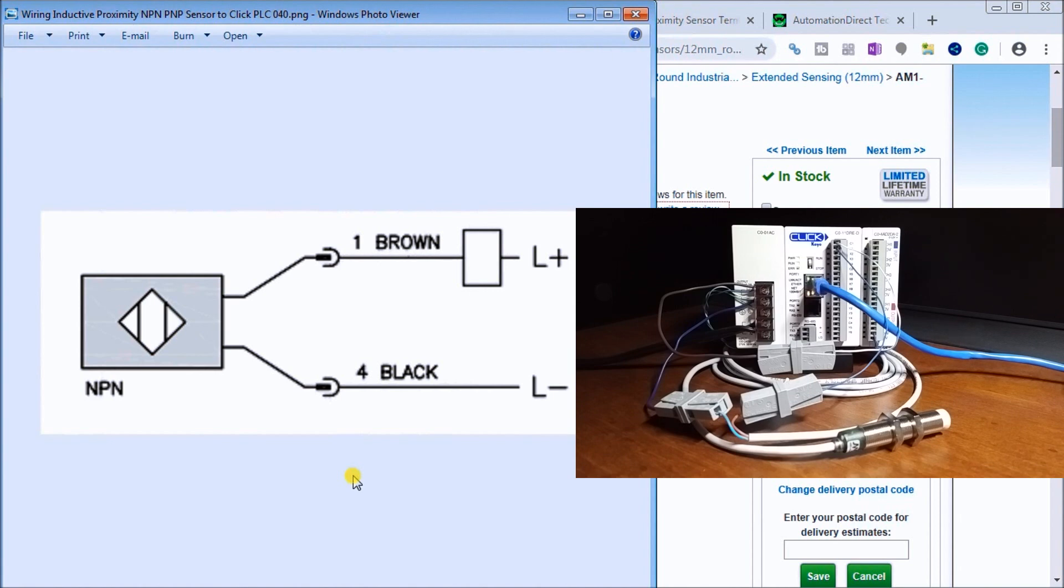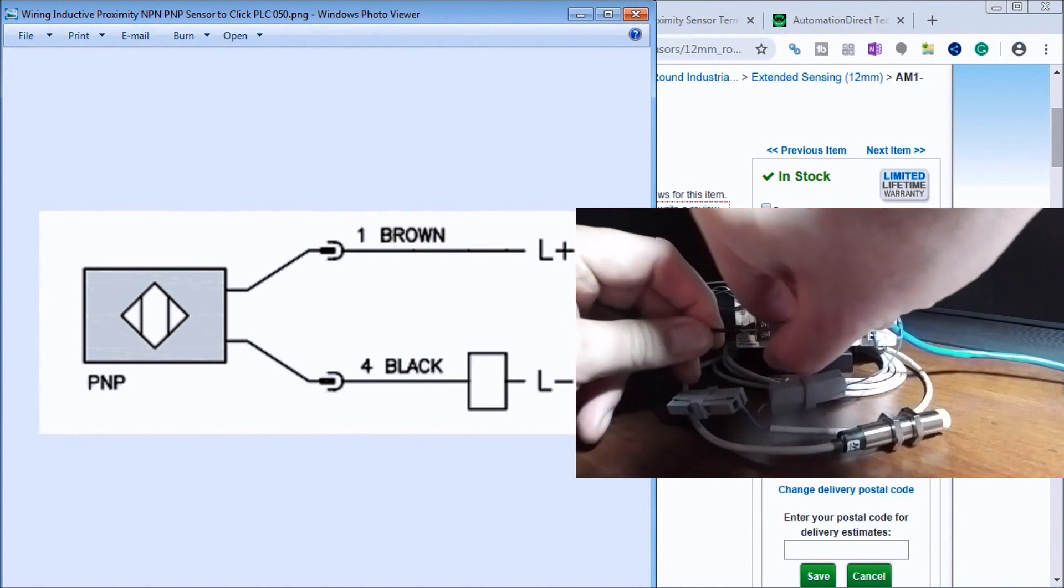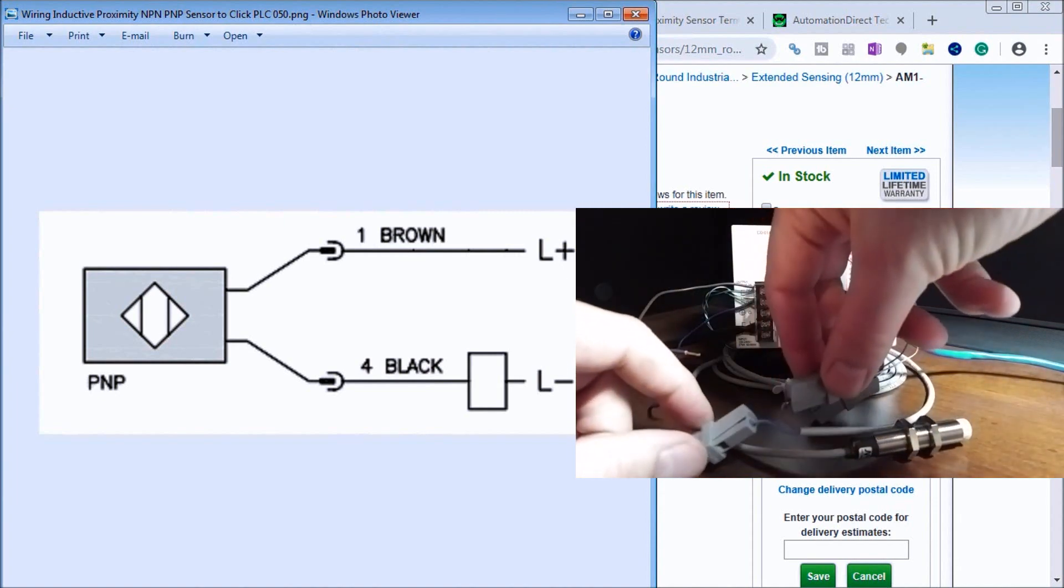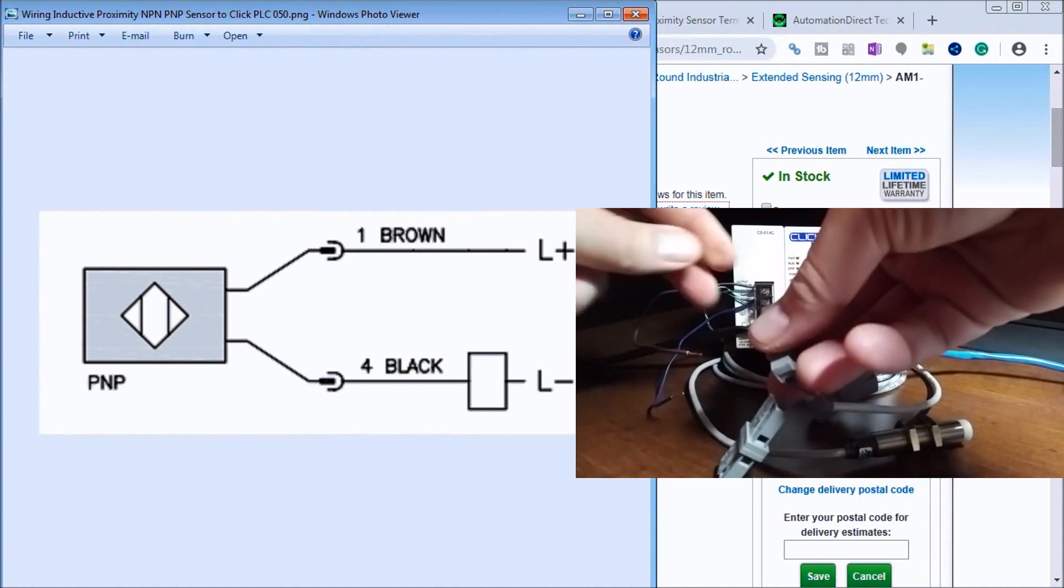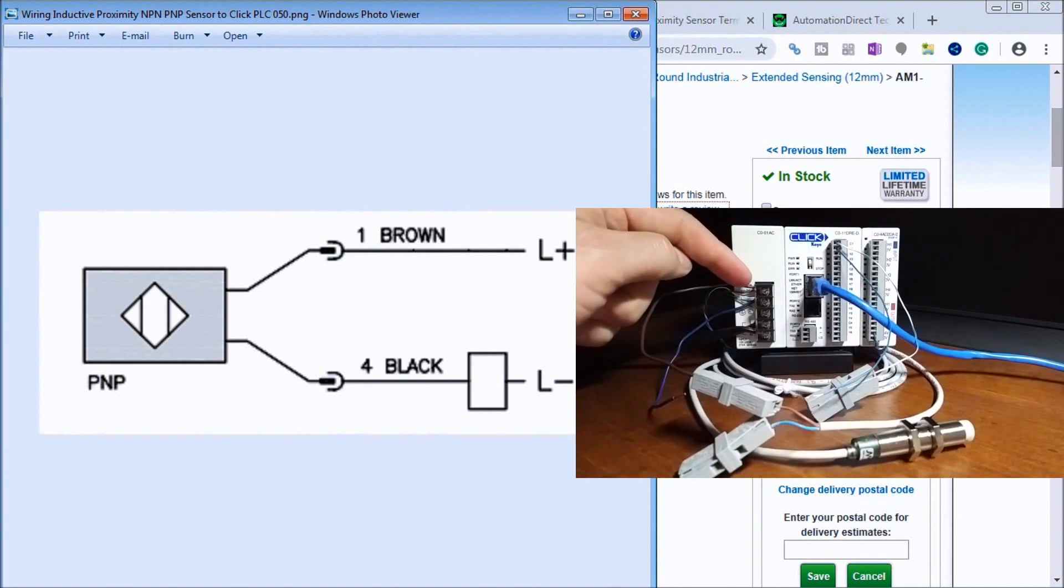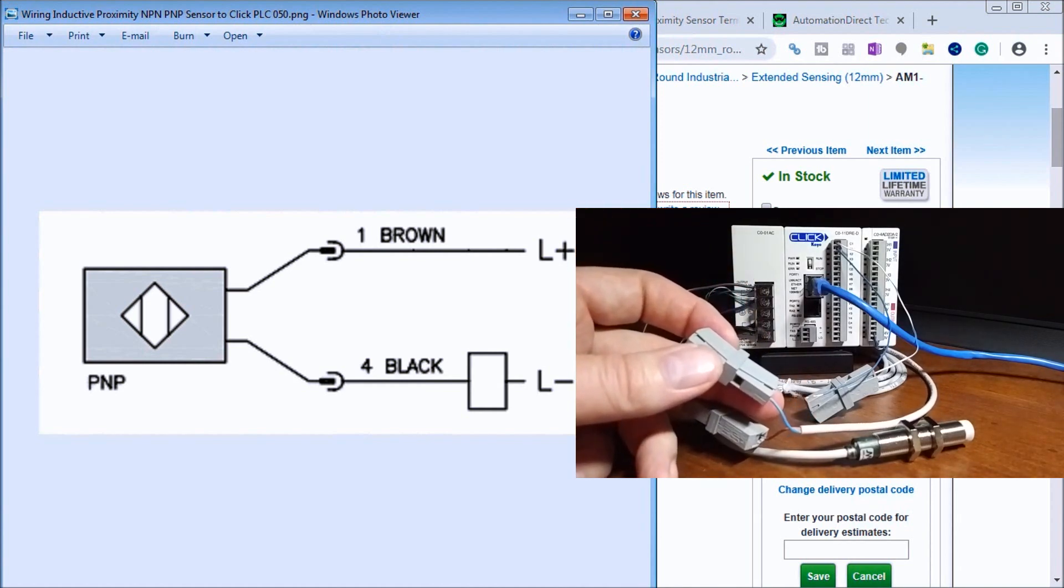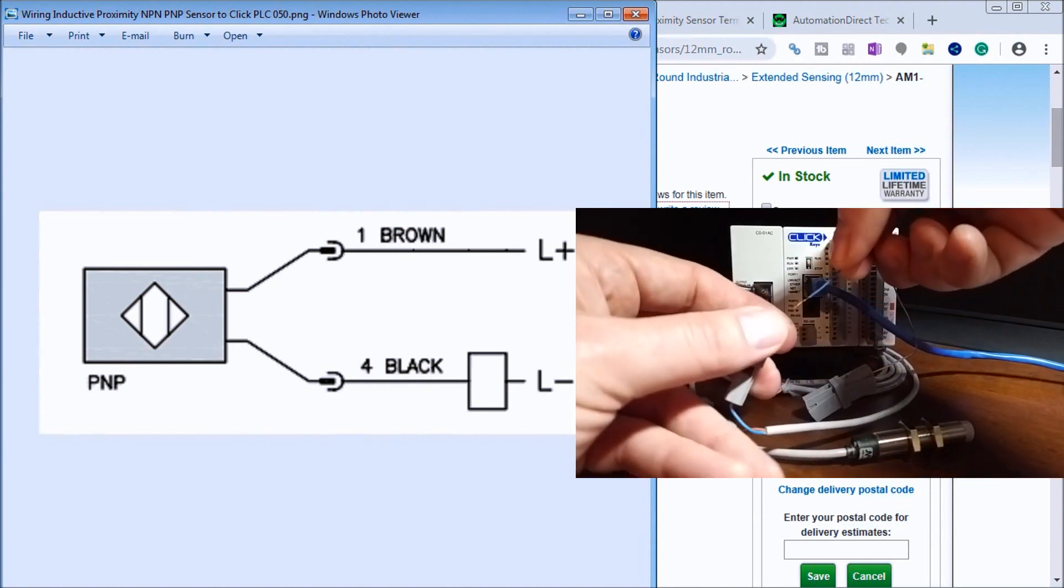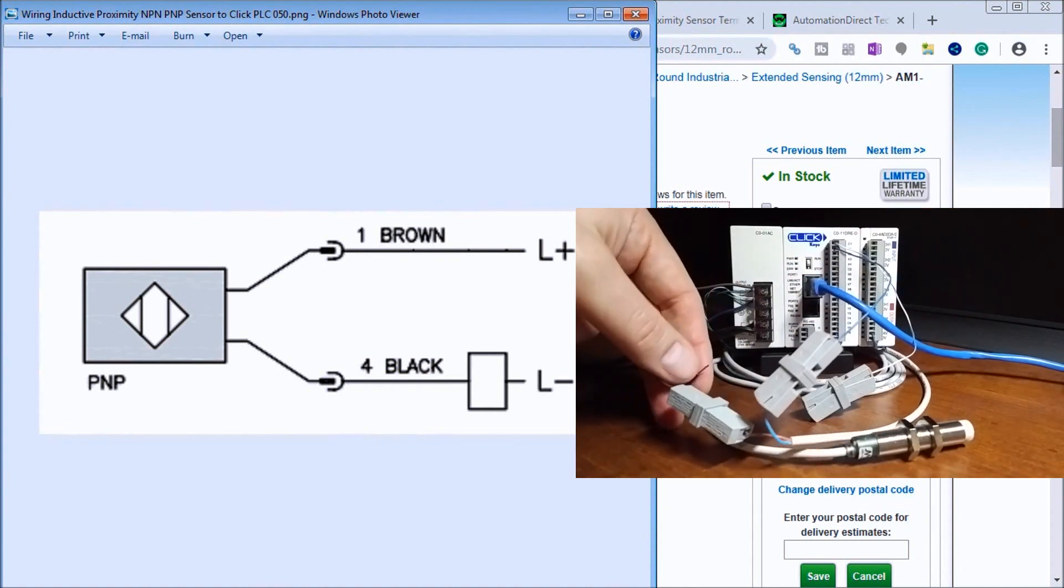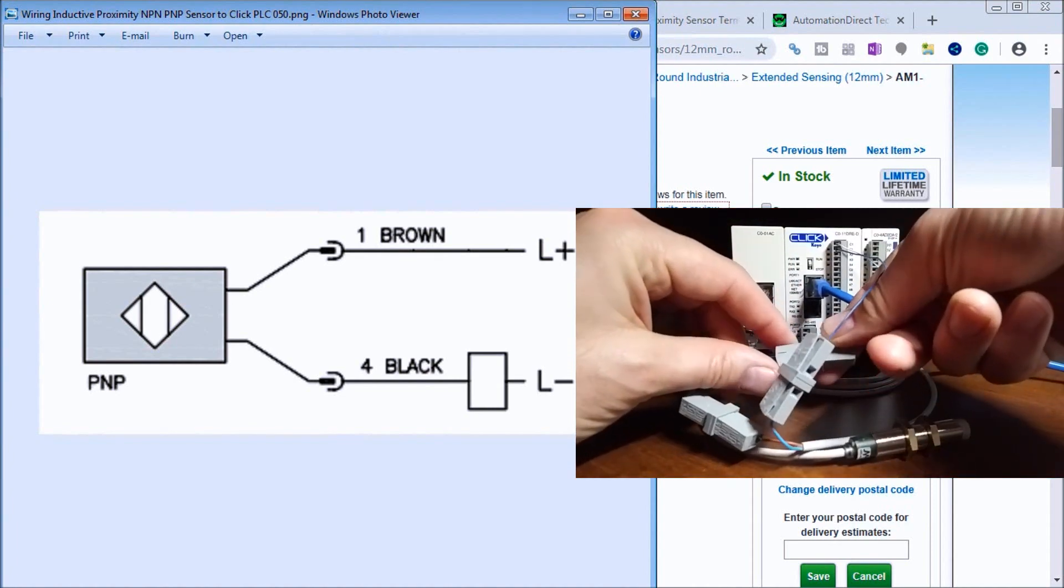Now if we remove power, we will rewire this for PNP. The first thing we'll do is disconnect these sensors. We will take our brown wire and connect it directly to our plus voltage. Then our black wire will go to our input and our common or zero volt will go back to our common in our PLC.